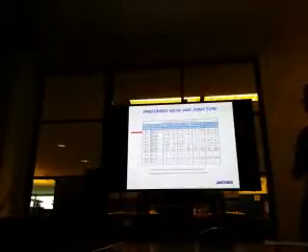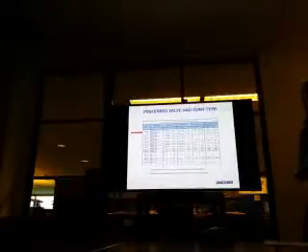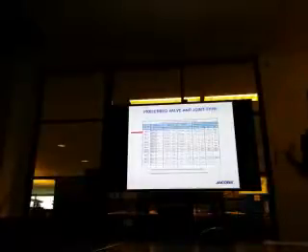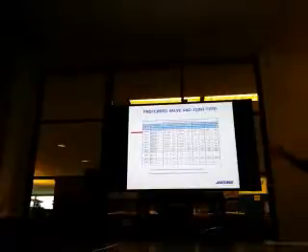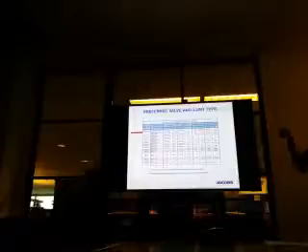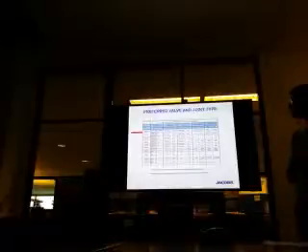Third item here is block valves. The three most common types of block valves in non-hygienic services are gate valves, ball valves, and butterfly valves. And sure enough, in this specification, we have all three. So you have to figure out which one we want to use. That's why we have this table. Small bore, we're using ball valves. Pretty much in gases and in water services, we like to have a quarter-turn block valve. And that's what a ball valve is. And I'll show you a sample in a little bit. For the larger sizes, we're using a butterfly valve.